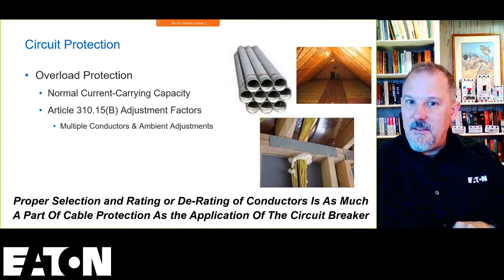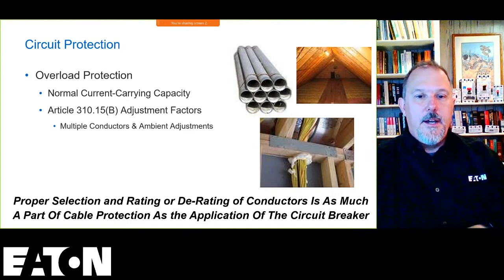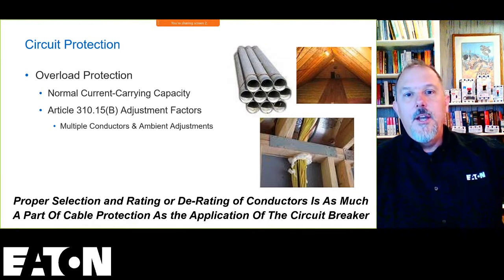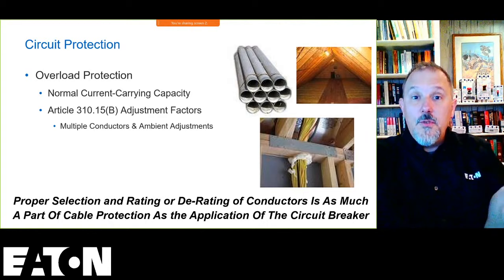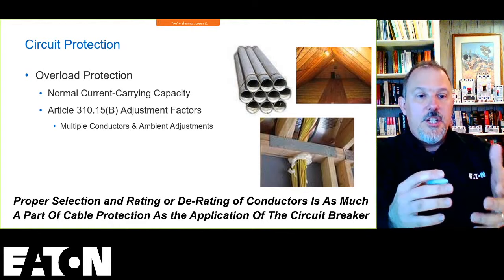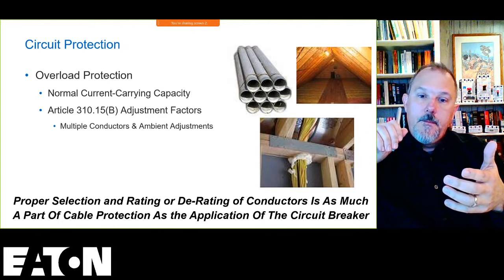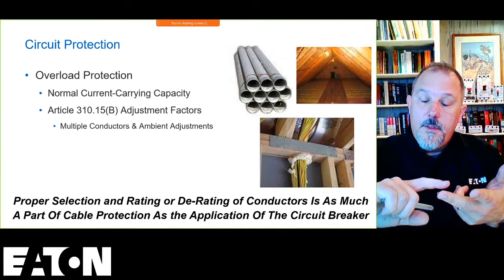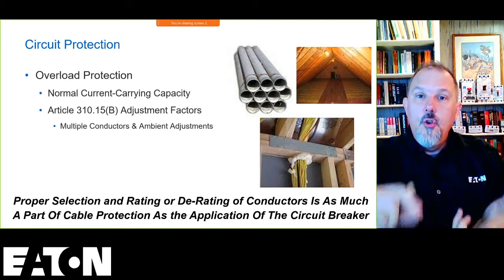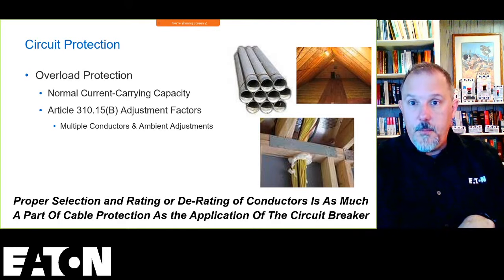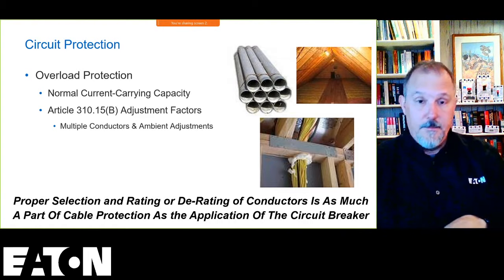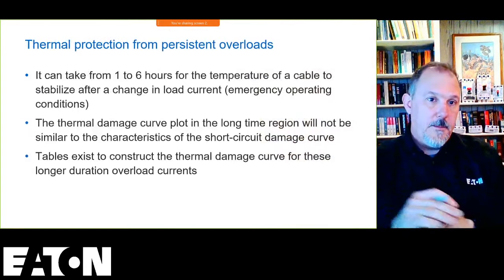You're going to adjust the ampacity based upon those conditions of use, and that helps you understand what the ampacity is, which will lower that number. Because if you don't adjust for the temperature of the environment, nor the number of conductors in a raceway, normal load currents could be an overload for that conductor based on its conditions of use. So you need to make that adjustment.